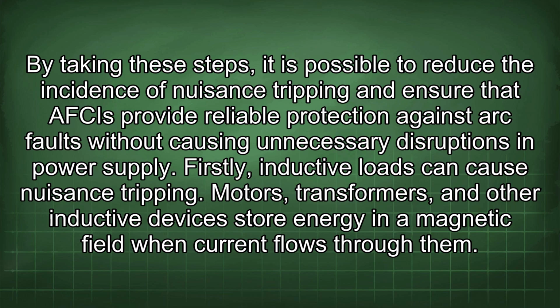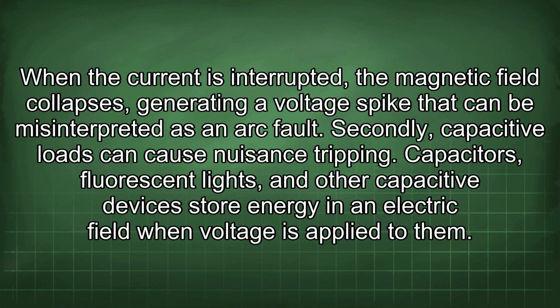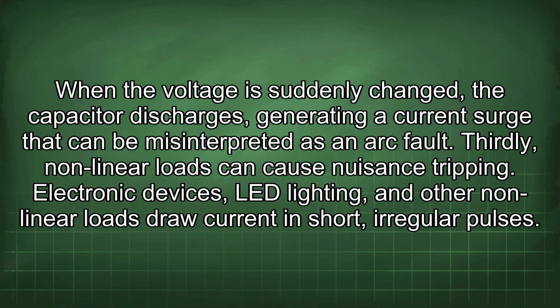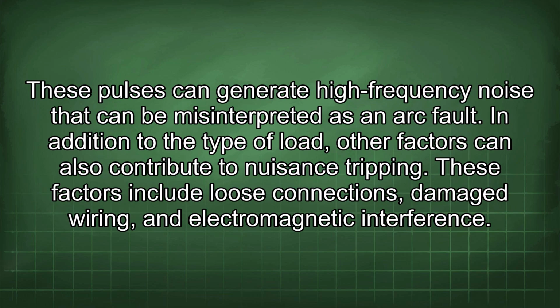Firstly, inductive loads can cause nuisance tripping. Motors, transformers, and other inductive devices store energy in a magnetic field when current flows through them. When the current is interrupted, the magnetic field collapses, generating a voltage spike that can be misinterpreted as an arc fault. Secondly, capacitive loads can cause nuisance tripping. Capacitors, fluorescent lights, and other capacitive devices store energy in an electric field when voltage is applied to them. When the voltage is suddenly changed, the capacitor discharges, generating a current surge that can be misinterpreted as an arc fault. Thirdly, nonlinear loads can cause nuisance tripping. Electronic devices, LED lighting, and other nonlinear loads draw current in short, irregular pulses. These pulses can generate high-frequency noise that can be misinterpreted as an arc fault.